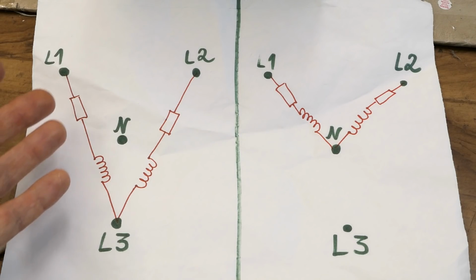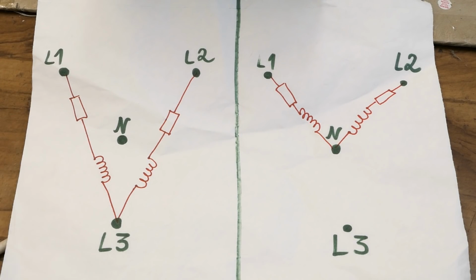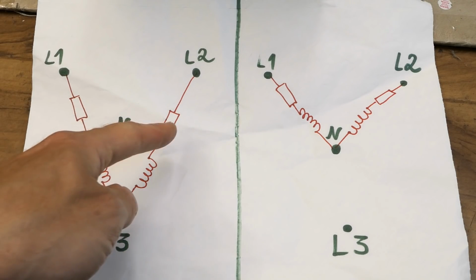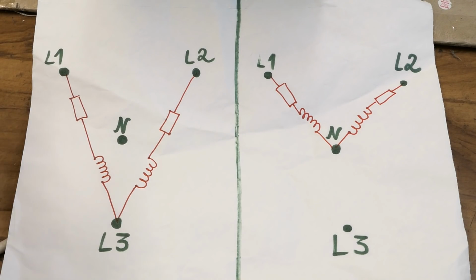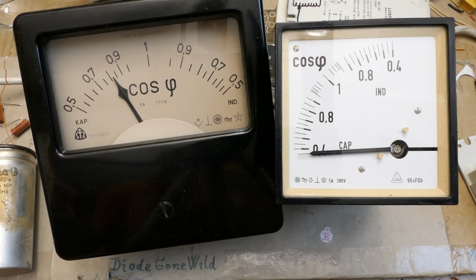And the 3-phase ones are not skewed by the frequency variation simply because they are using just resistive droppers, no inductors or capacitors in series with the coils. But I have to stress that these machines are measuring the power factor based on the phase shift between the current and the voltage. These basically work for linear loads, which don't distort the sine wave, they just shift it. So the current sine wave is ahead or behind the voltage sine wave. They don't measure the power factor of harmonically distorting loads, for example rectifiers in switching power supplies or other devices.